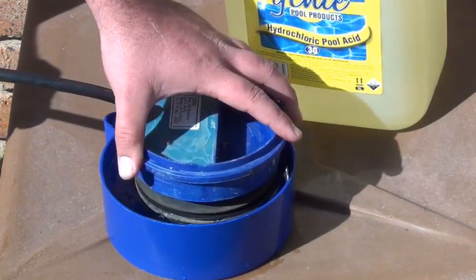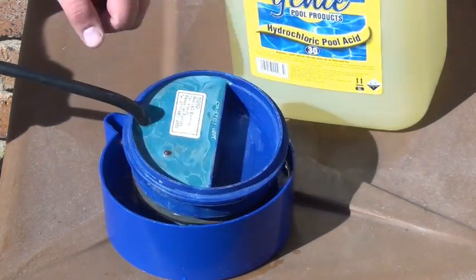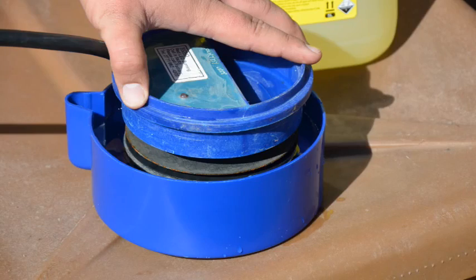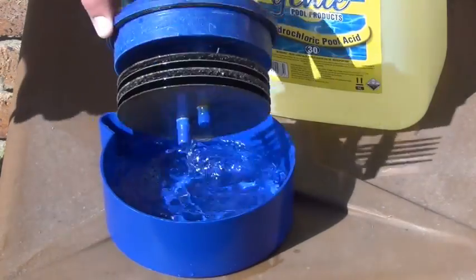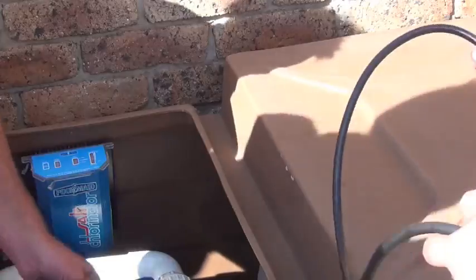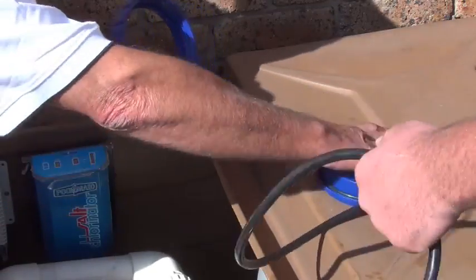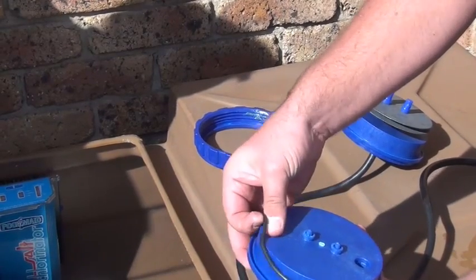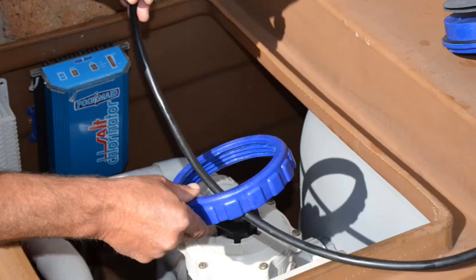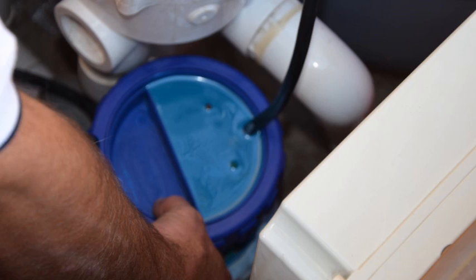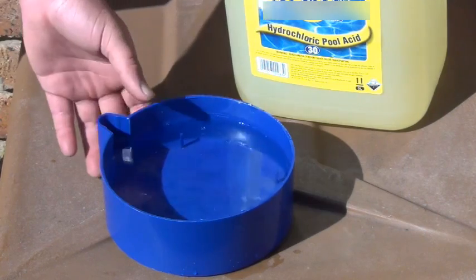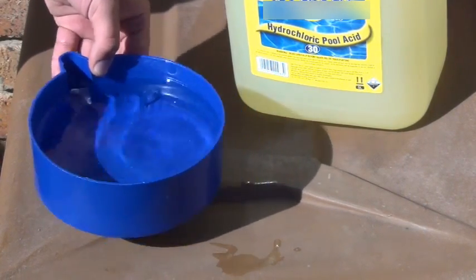Do not scratch or damage the cells with any sharp object. After soaking for 10 minutes, remove from bowl and replace cells. Ensure the O-ring is secure and not damaged. Hand tighten the ring nut. Switch the power back on and dispose of hydrochloric acid mixture.